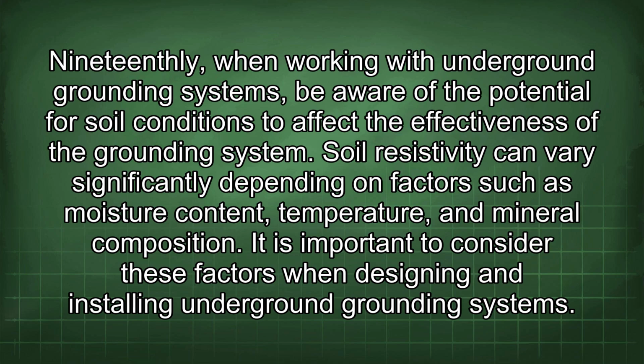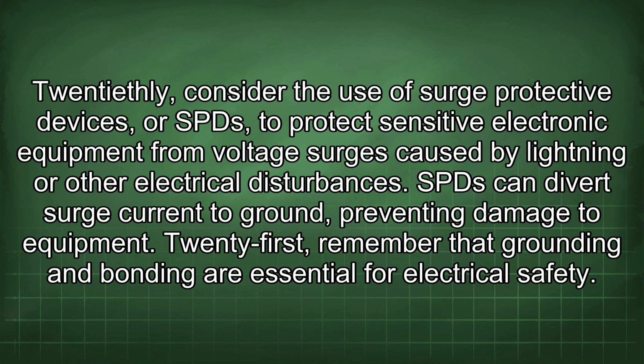19thly, when working with underground grounding systems, be aware of the potential for soil conditions to affect the effectiveness of the grounding system. Soil resistivity can vary significantly depending on factors such as moisture content, temperature, and mineral composition. It is important to consider these factors when designing and installing underground grounding systems. 20thly, consider the use of surge protective devices, or SPDs, to protect sensitive electronic equipment from voltage surges caused by lightning or other electrical disturbances. SPDs can divert surge current to ground, preventing damage to equipment.